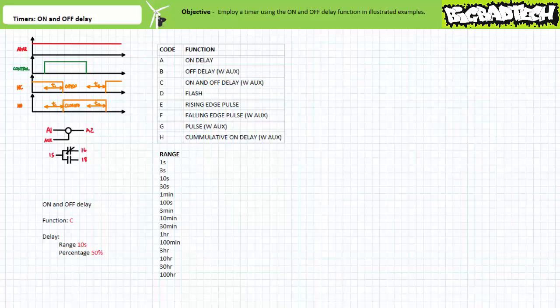Troubleshooters take note: a multifunction timer executing the right function at the wrong time needs to have the delay adjusted; a multifunction timer executing the wrong function at the right time needs to have the function adjusted. A misinterpretation of functions is not a rare occurrence — you need to be aware of this possibility. Multifunction timers executing the on and off delay are often represented schematically as regular normally closed or normally open contacts, and the documentation associated with the ladder logic diagram should clearly indicate they are performing the on and off delay function.